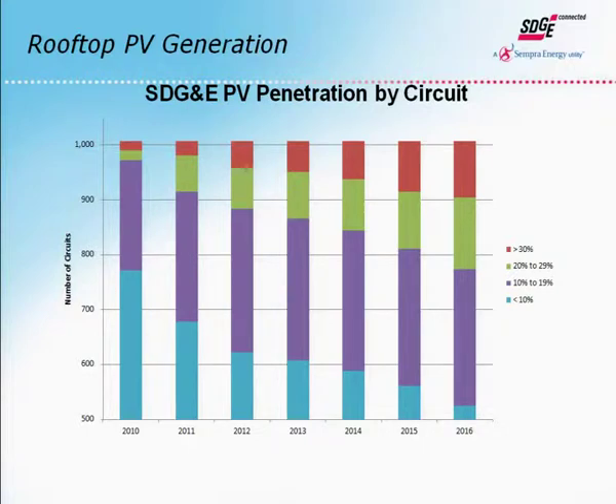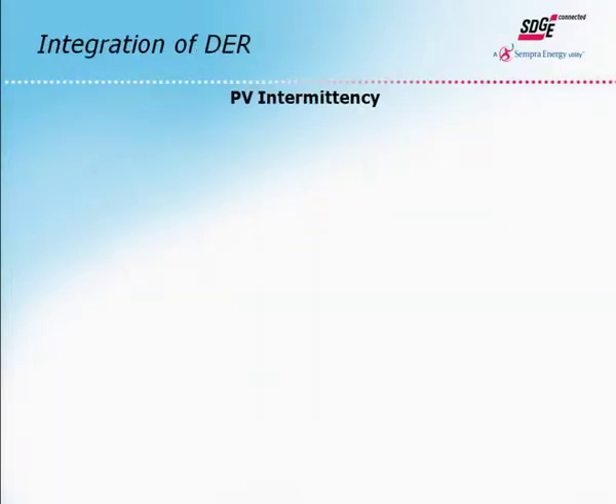The bigger challenge for a utility like us is when PV output is high and the load isn't very large, or there isn't a lot of air conditioning on. So in the April, May timeframe, around 1 o'clock in the afternoon, if you're oriented due south, once we start seeing penetration levels exceeding 30% on a particular circuit, we start to see problems with performance on that circuit. I'll show you some slides.